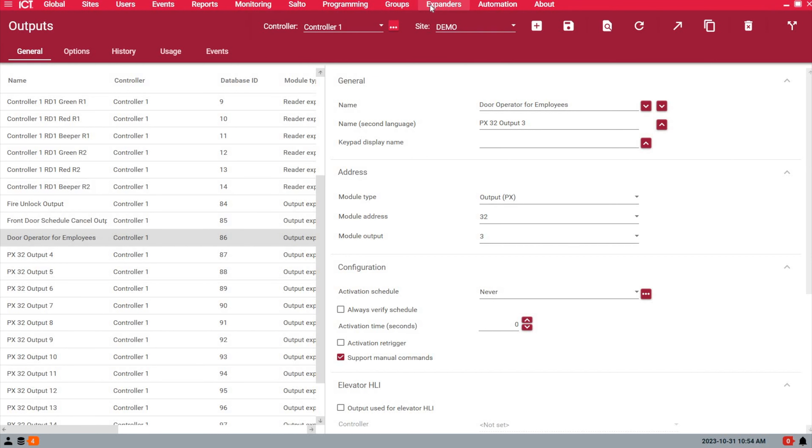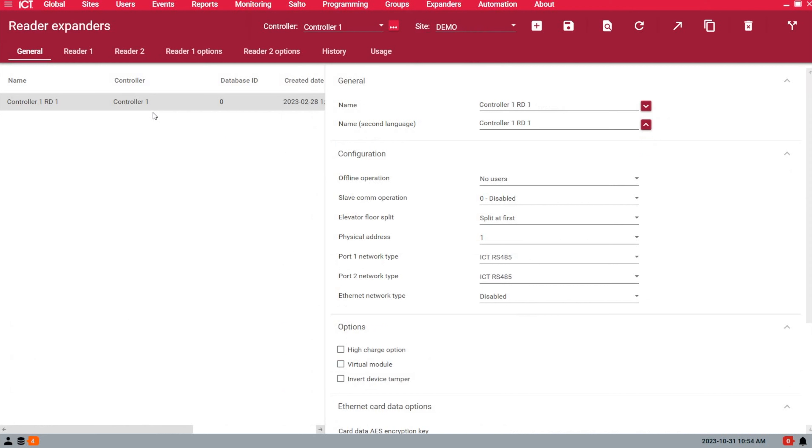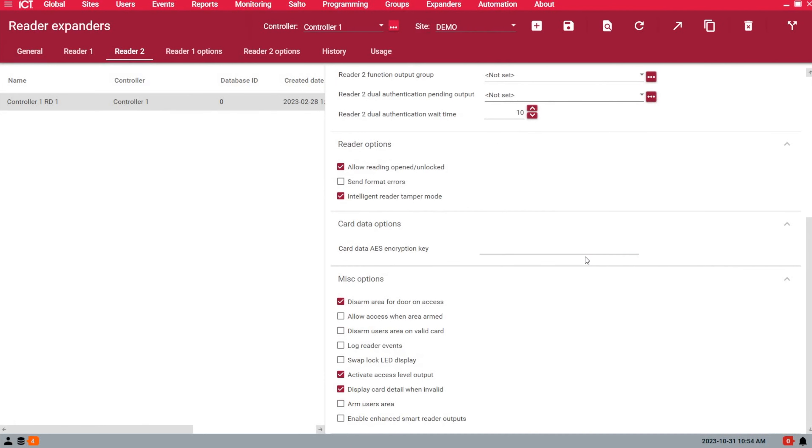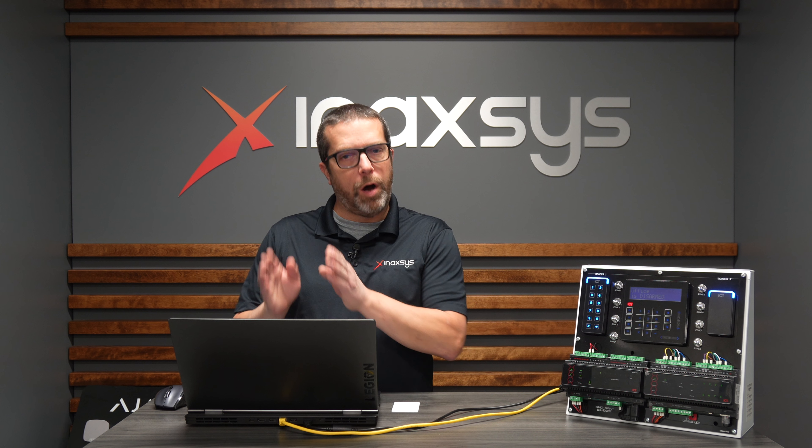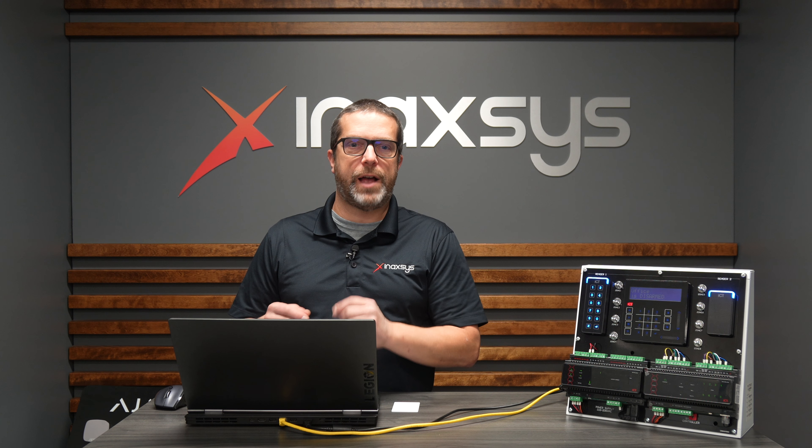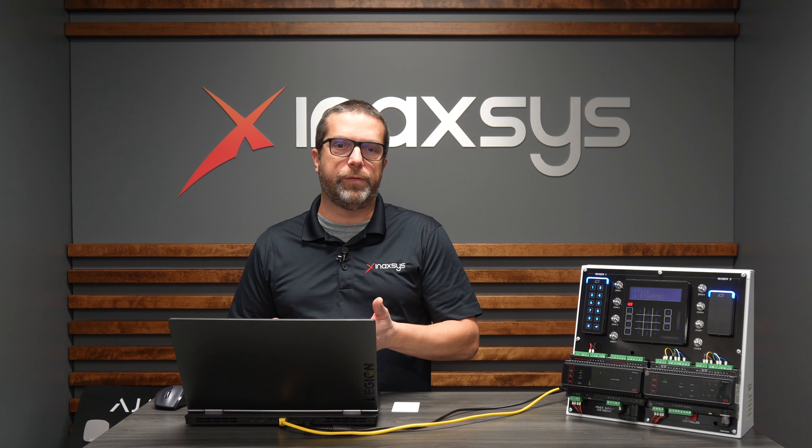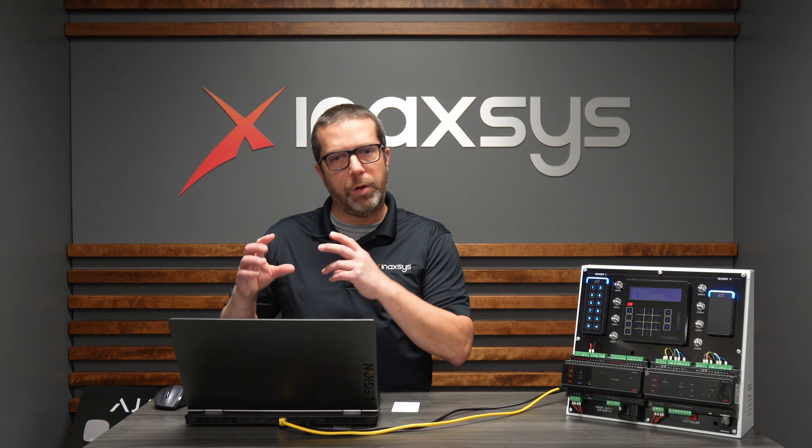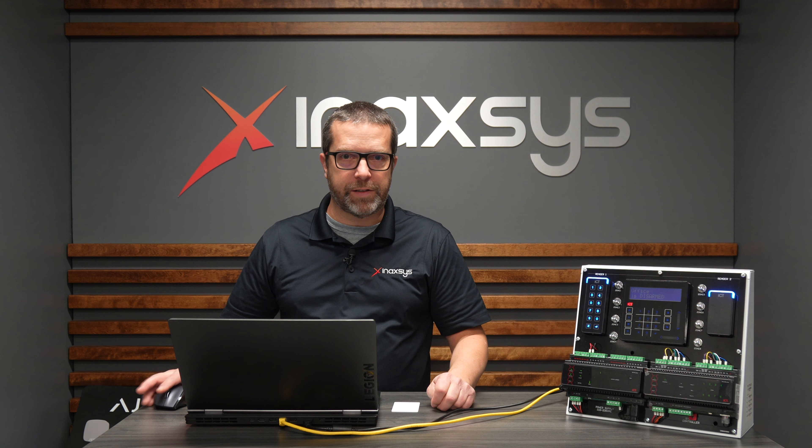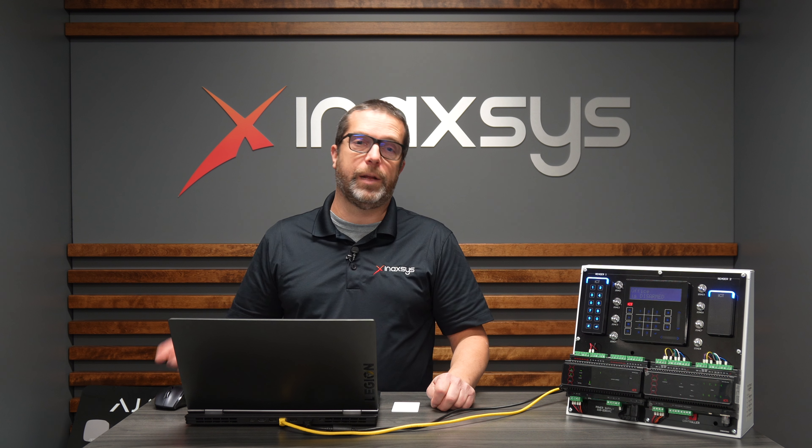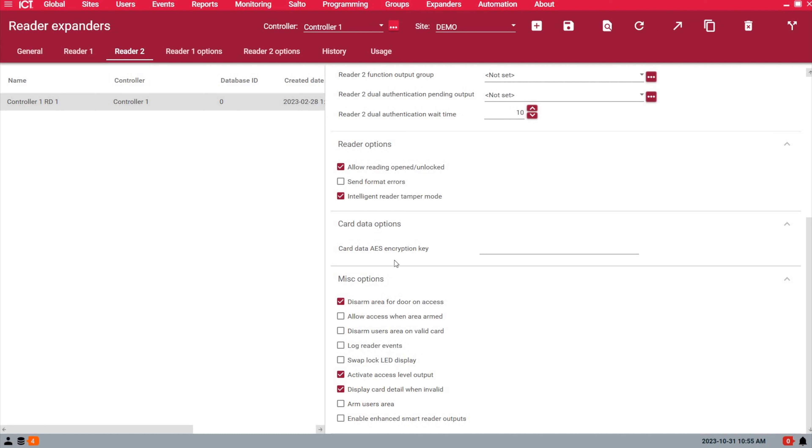In the reader expander properties, I'm using reader port number two for the employee entrance door. To get there, go under Expanders and Reader Expanders. Under Reader 2 at the bottom, you'll see the 'activate access level output' option - the fourth option from the bottom. By activating this, you're telling the system that on that reader port, if a user has the access level output feature enabled, activate the output assigned to the access level. This can be one or multiple outputs.